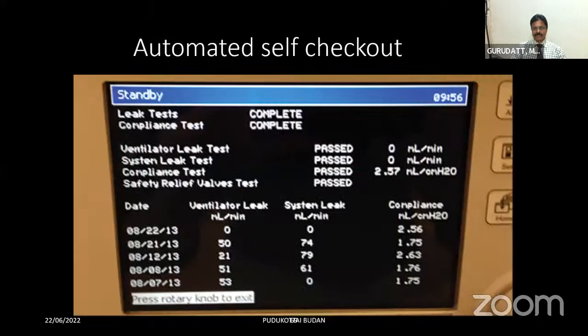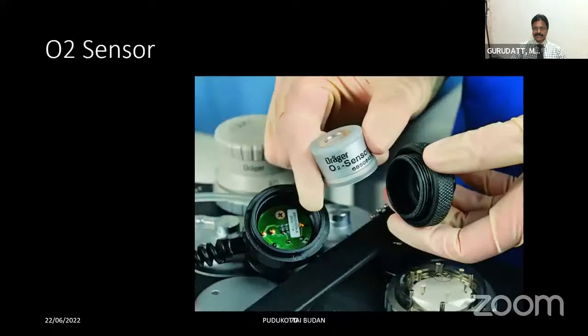In modern workstations, you have automated self-checkout tests. But if you have a check valve, it is better to use the negative pressure leak test before going in for the automated self-checkout. Whatever it may be, a hypoxic mixture can still be delivered to the patient. That's why you should always have an oxygen sensor at the inspiratory limb, so that you know what FiO2 the patient is getting.